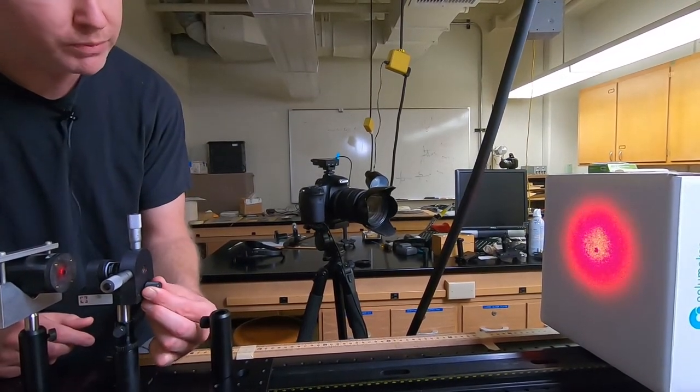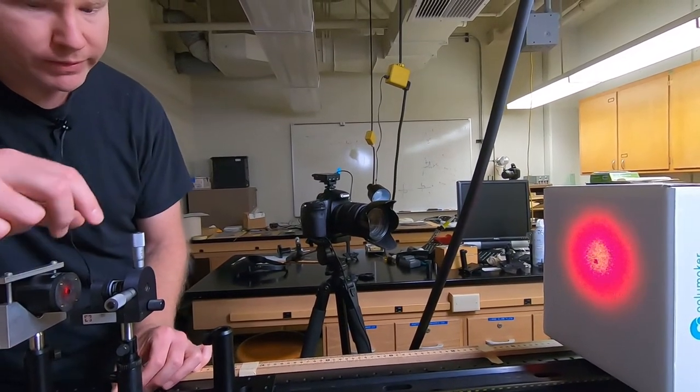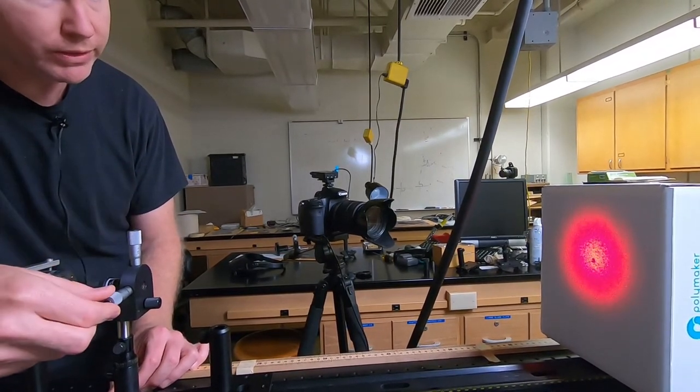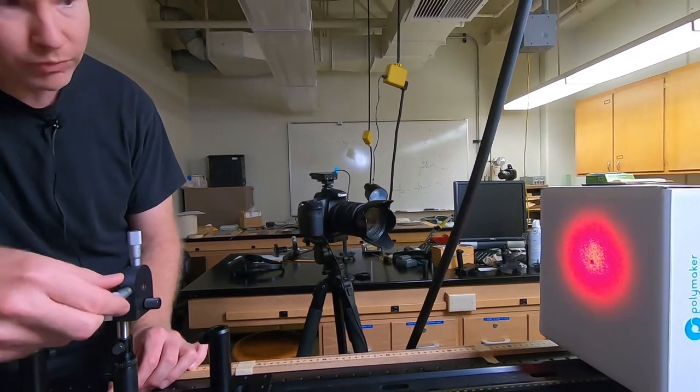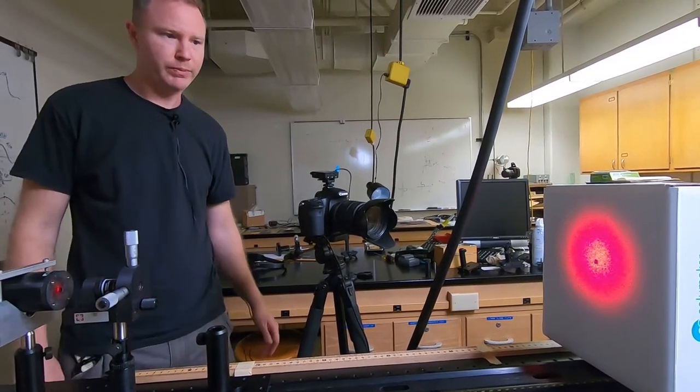I'll do some final X and Y and focus adjustments just to make it look as uniform as possible, centered around where the laser was going. That's how you adjust a spatial filter.